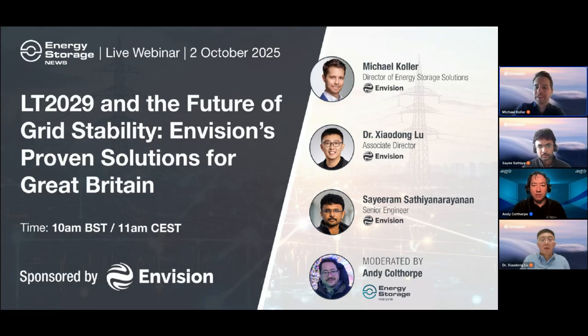Yeah, if I can take that one, it's a good question. I think Xiaodong alluded to two key concepts just before in his answer. For short circuit level, it's mainly reactive power, so you mainly need to look at the AC components, right? The DC cells themselves are not really affected. You need to make sure your AC components are properly sized, and with the grid forming control, you limit at the right points in time. So the lifetime of your AC components is not impacted.